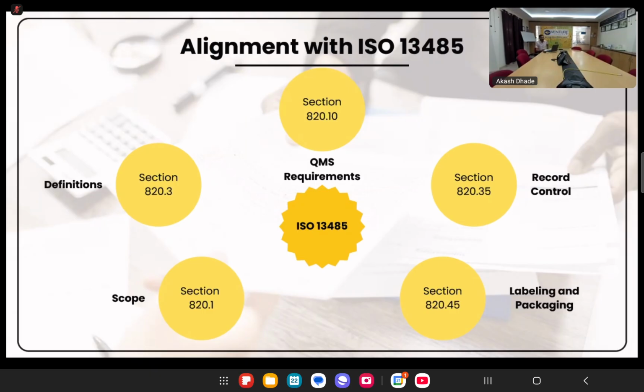Okay. For example, your medical device has a complaint, and you want to investigate that complaint for its root cause, and after doing the root cause, you come to the conclusion for certain design changes. And with respect to that, you also raise certain CAPA, corrective and preventive action. So in order to do that, you should have a record of each of these activities. Say, for example, in this process of finding out a complaint, you should have a procedure and a record wherein that complaint was recorded. After that complaint was recorded, you will initiate the root cause analysis first. So through record control, you will record what root cause analysis was done. What was the team for root cause analysis? What was the technique of root cause analysis?